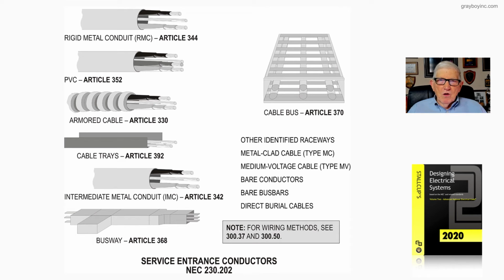Now, but when you start picking up components to use with these wiring methods, switchgear, switchboards, panelboards and things like that, circuit breakers, fuse arrangements that you might want to use for protection, you have to go to Article 490 for those. So you're using Article 311 for the ampacity of conductors, and you're also using the requirements in 311 that used to be in Article 328 for medium voltage, but you must go to Article 490 to select the equipment and the components to make up a high voltage electrical system.